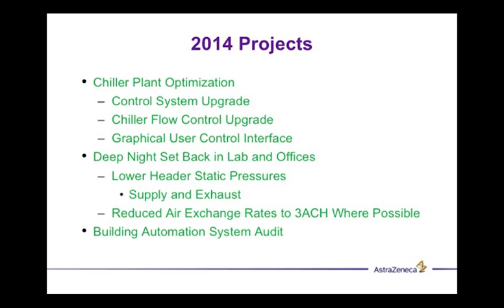Because when they first balance the building, the balancer is going to go in there and whip open all the valves, and you're going to say, I need 2.5 inches static pressure in the main header. Well, you don't need it at 3 o'clock in the morning. And it's very important to know. So we reduced the air exchange rates to 3 air changes an hour at night. We found we can go to 0.9 inches of static pressure in the main headers.